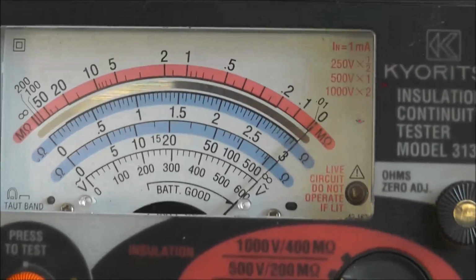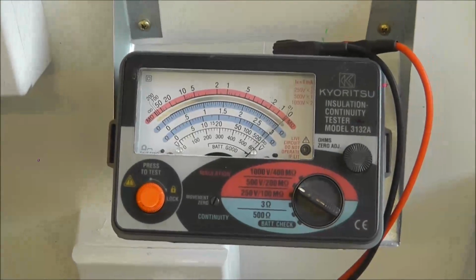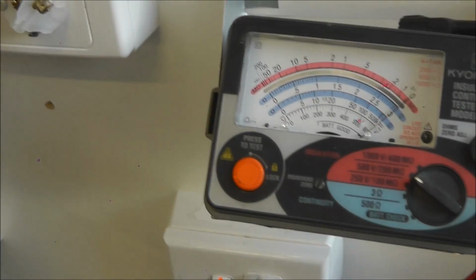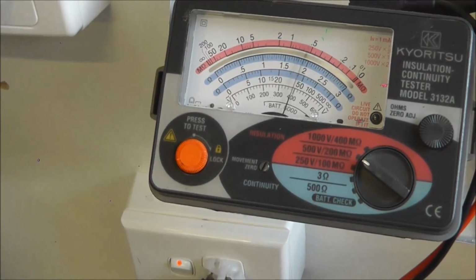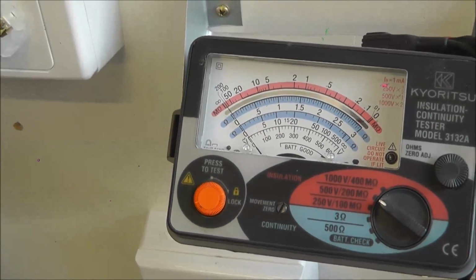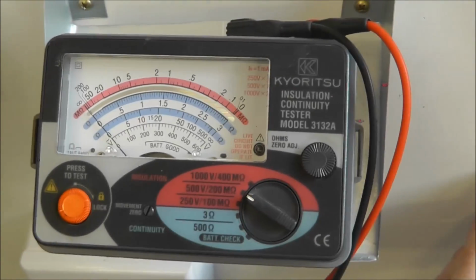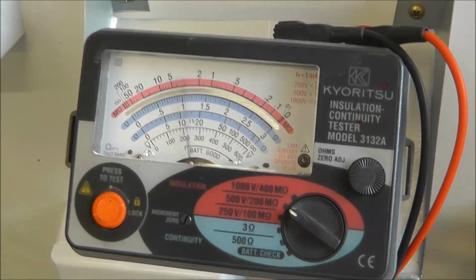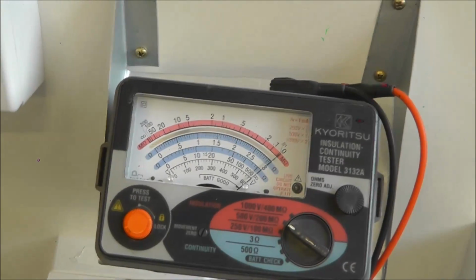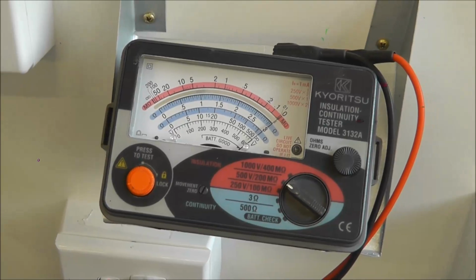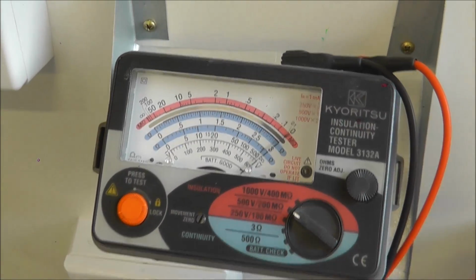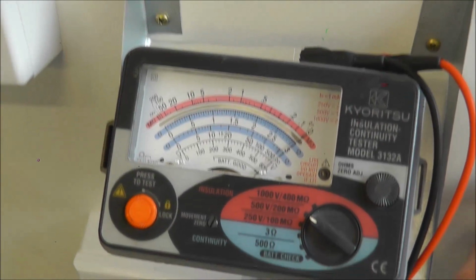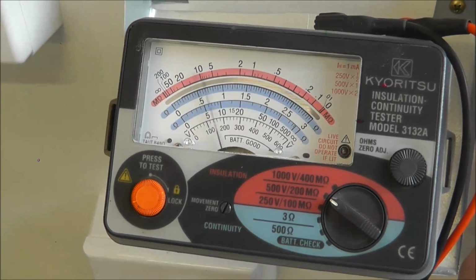Now, Dobbo, just as an investigation here, just flick those light switches off there. Just flick them off. And all of them. Oh, now see that? That fan one there. Flick that fan back and forwards. Isn't that interesting? So as Dobbo's flicking the switch, it's going fault, clear, fault, clear, fault, clear. So you'd have to be making sure, wouldn't you, that...